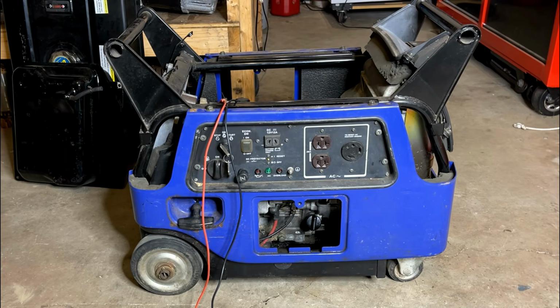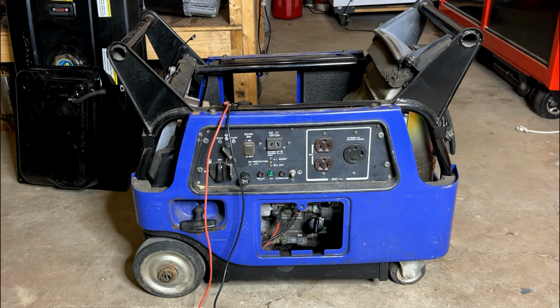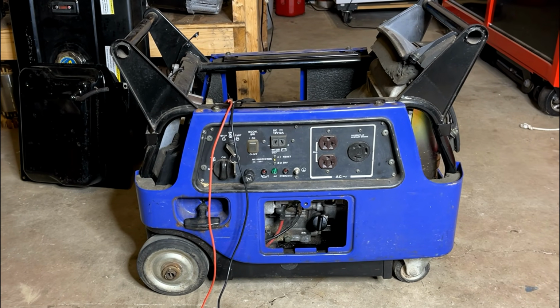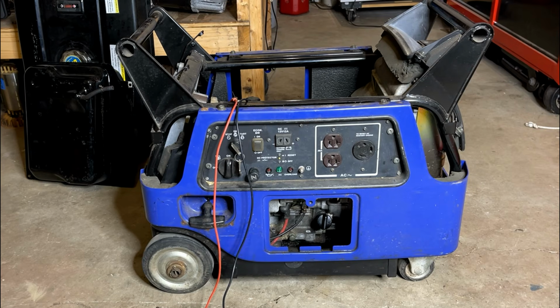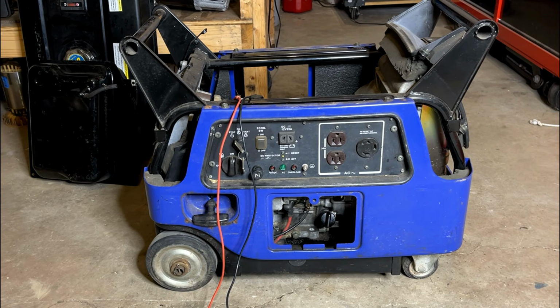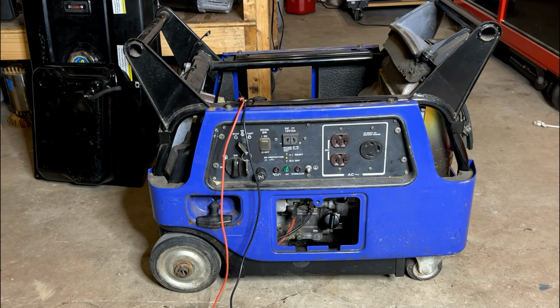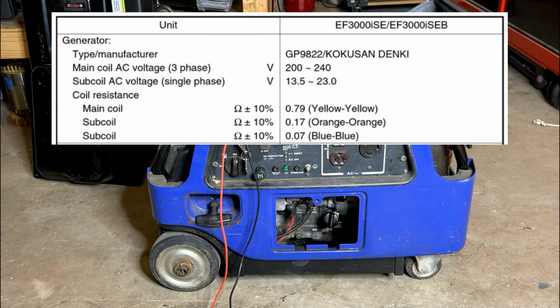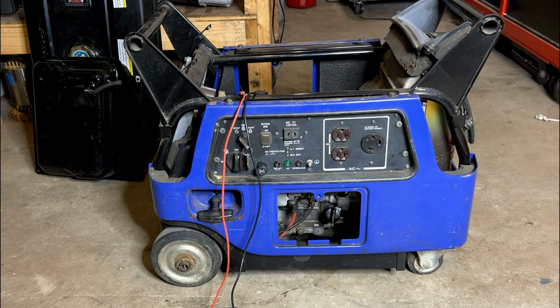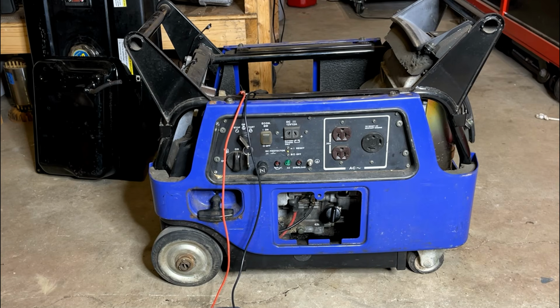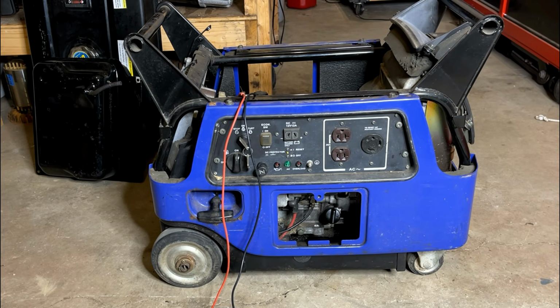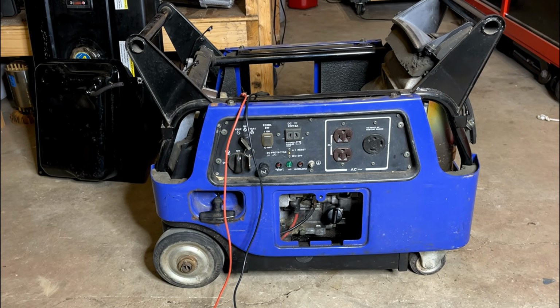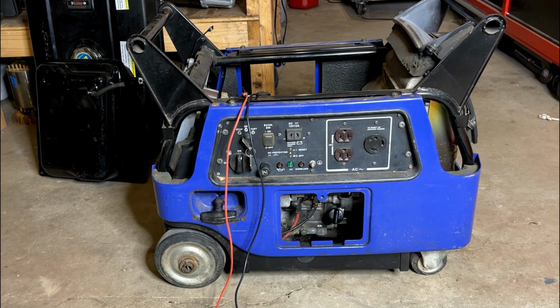It's been a couple days and I've done my homework. I managed to locate the service manual and it had some useful information. First off, it had a resistance table of expected values on a healthy stator for both the main 3-phase coil and the secondary single-phase coils. The readings I got matched the service manual perfectly, so I think we're good there.